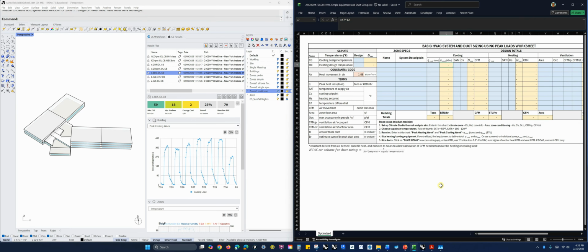So we're talking about moving air. You don't really need to know the details of this, but if you think about it, we're going from Q, which is heat or energy, in kilobtus per hour, and then we need to know how much air we can move in order to move a certain number of kilobtus per hour. So we need a constant, which is what this 1.08 is, that allows us to determine how much heat a given volume of air can move, like a unit of air. And here's an equation down here saying how that works. You can ignore that if you want to. Let's just dive right into it.